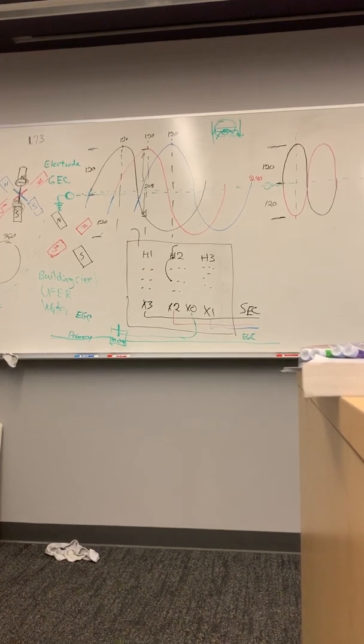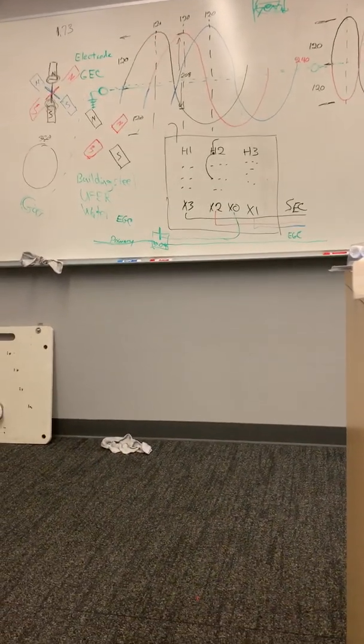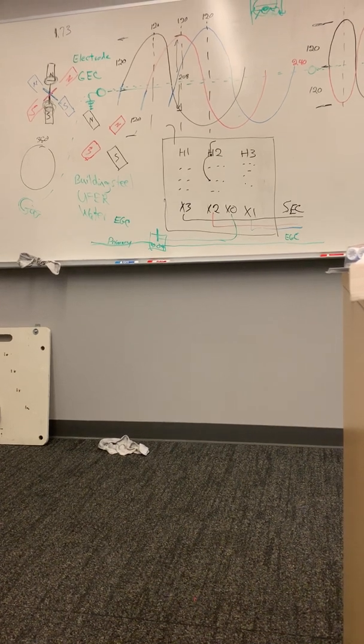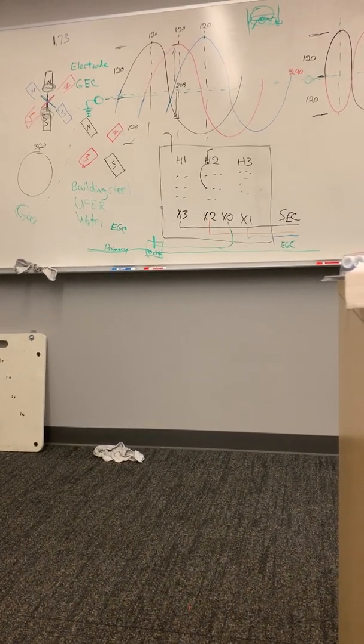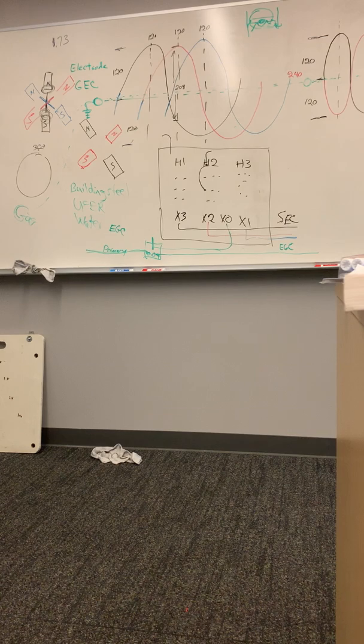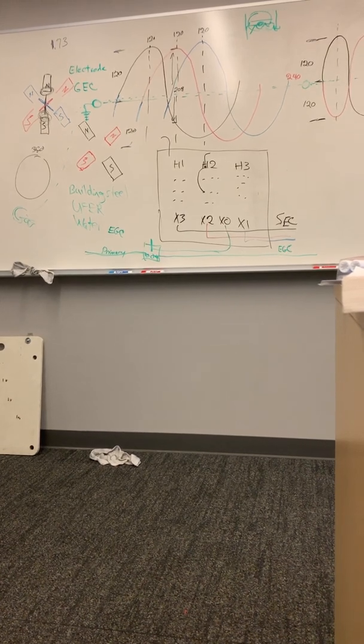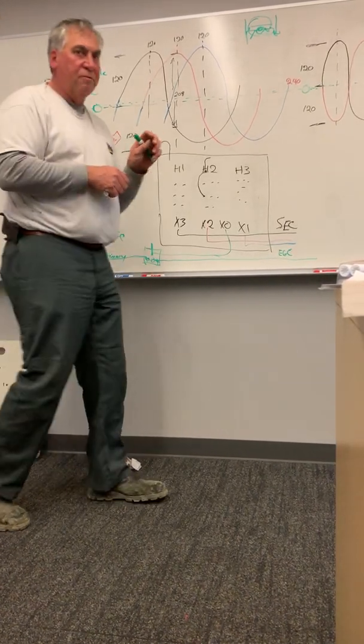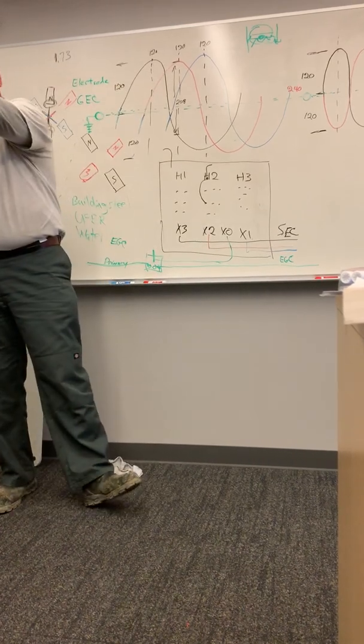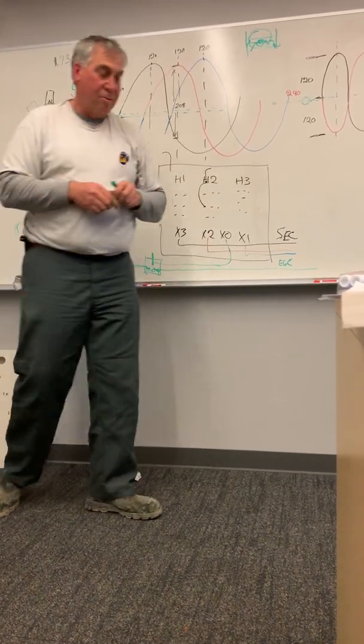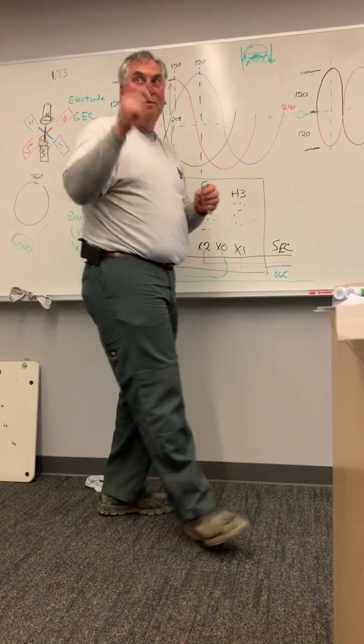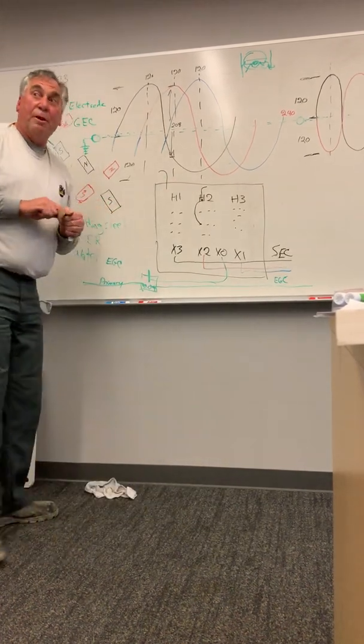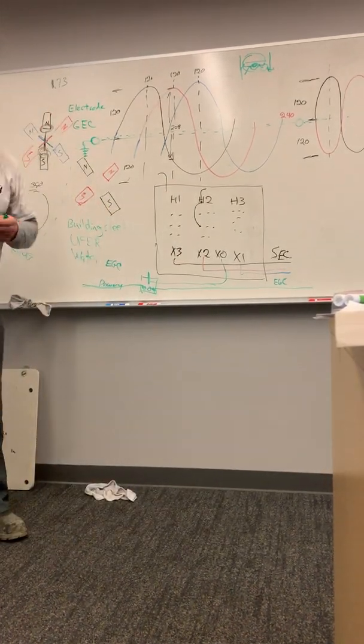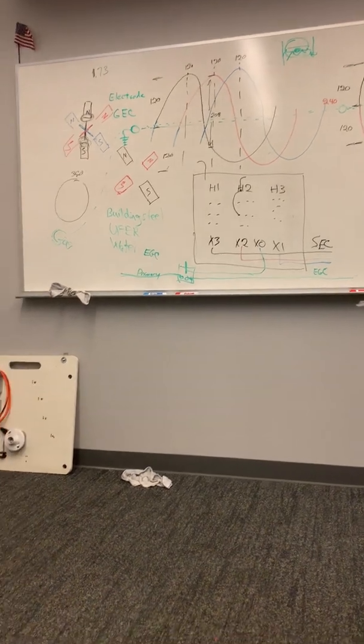Question: we're doing a 300 kVA, I believe, and we're just running 2 parallel 250s. Do you have to run a ground for both? You're running parallel 250s to a 300 kVA transformer, with a total of 500 kcmil, right? That's a good question. And they're in parallel. Yes. All right, so now I'll go over here.